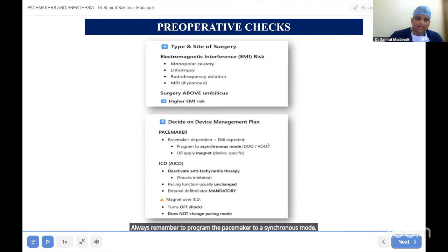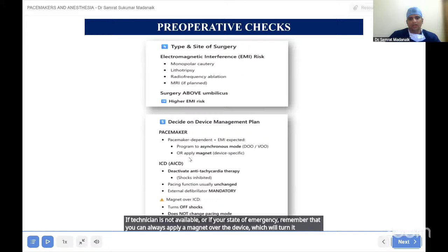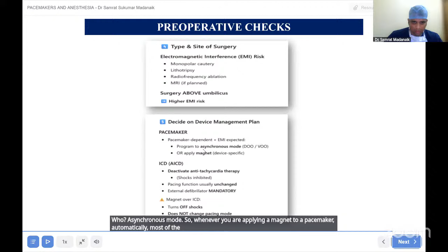The fifth important part is that you have to decide on the device management plan. If the patient is pacemaker dependent and EMI is expected, always remember to program the pacemaker to asynchronous mode. If a technician is not available or if you are in a state of emergency, you can always apply a magnet over the device, which will turn it to asynchronous mode. Whenever you apply a magnet to a pacemaker, most devices will automatically go to asynchronous mode. That is, the pacemaker is going to generate impulses irrespective of what it senses, so EMI will not interfere with the pacemaker function.